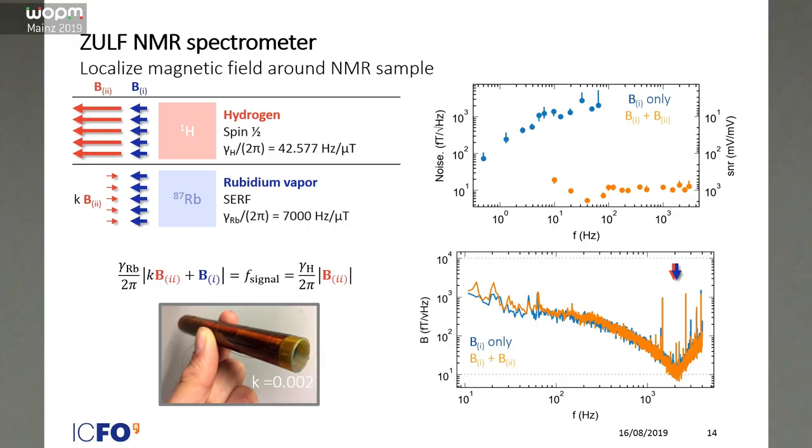You maybe think of putting an additional solenoid in the magnetic shield would produce or would create some additional noise. We actually measured the noise characteristics with only one field and with both fields, and we didn't see much of a difference. So that coil doesn't seem to produce much additional noise in the spectrometer.